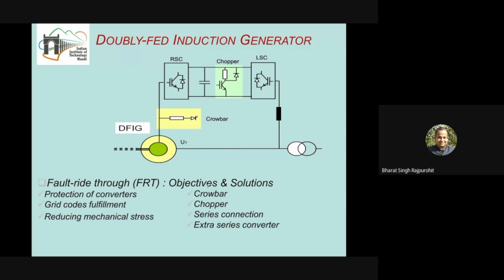During that operation, the power electronic components RSC and LSC are out of this circuit, and that's why this is generally known as short-term interruption, which is possible as per the German grid code. If you remember, this is what is known as short-term interruption. This is how severe faults can be ridden through. During the operation of this crowbar, the stator is connected to the grid and it is feeding the active power.